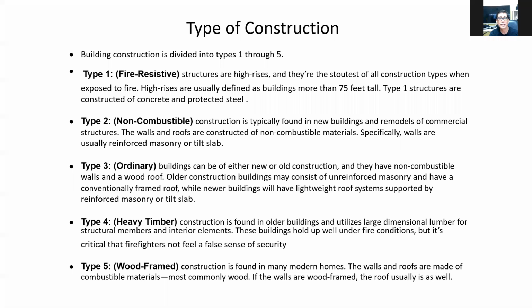Type 2 is construction typically found in new buildings and remodeled commercial structures. The walls and roof are constructed of non-combustible materials, especially walls, usually reinforced masonry or tilt slab. Type 3 is ordinary buildings, which can be of either new or old construction, and they have non-combustible walls and a wood roof. Another one is heavy timber construction, that's type 4. This construction is found on older buildings and utilizes large dimensional lumber for structural members and interior elements. And type 5 is wood frame construction found in many modern homes. The walls and roofs are made of combustible materials, most commonly wood. If the walls are wood frame, the roof is usually as well. So these are the different classifications of buildings in terms of fire protection based on type of construction.